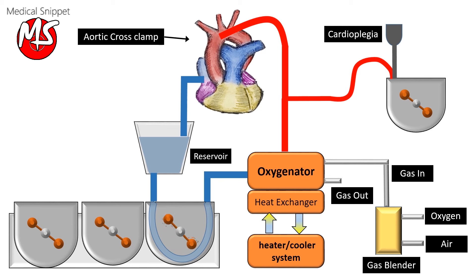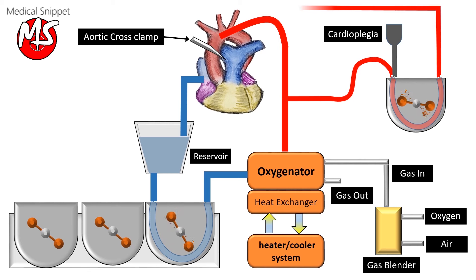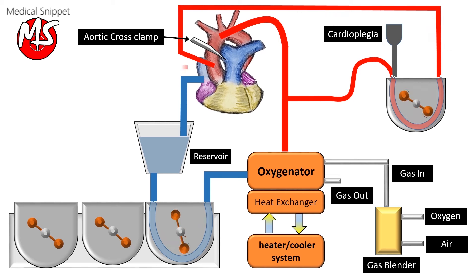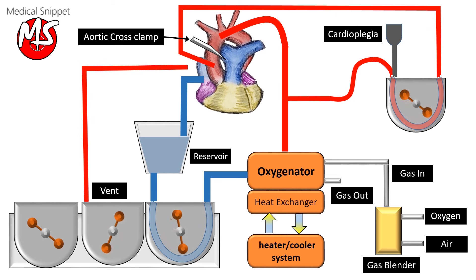After cross-clamping the aorta, the cardioplegia pump is run to deliver the cardioplegia to the aortic root through the cardioplegia delivery system, which contains a small heat exchanger, bubble trap, and temperature monitoring port. The blood from the vent cannula is returned to the venous reservoir.